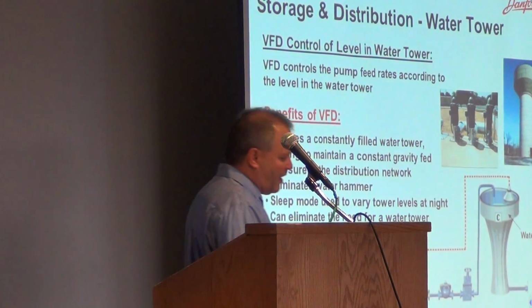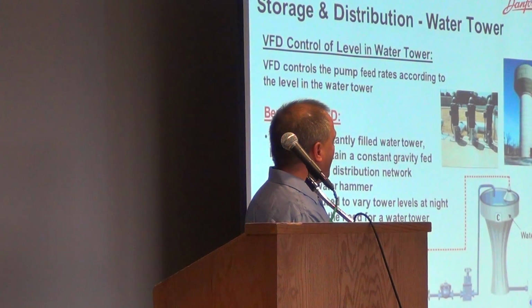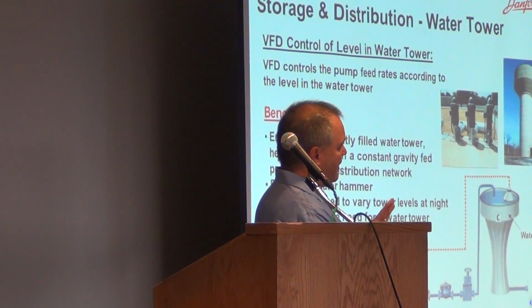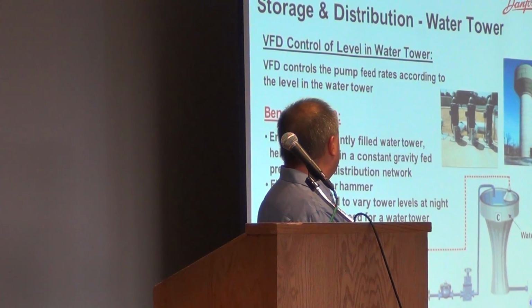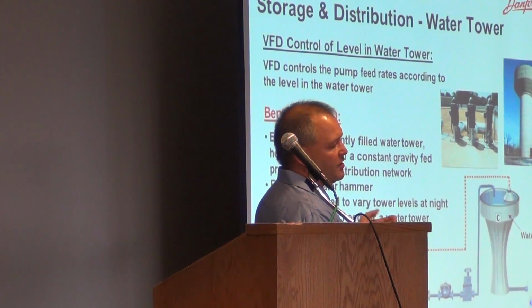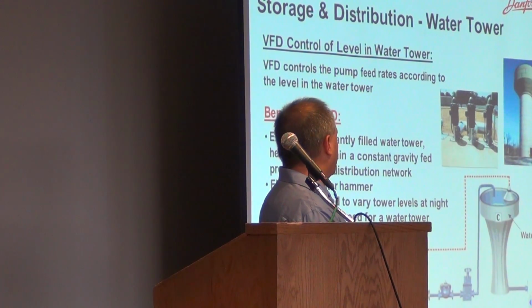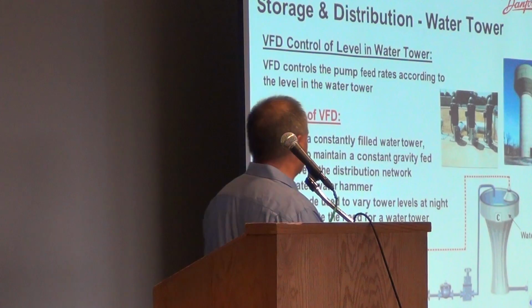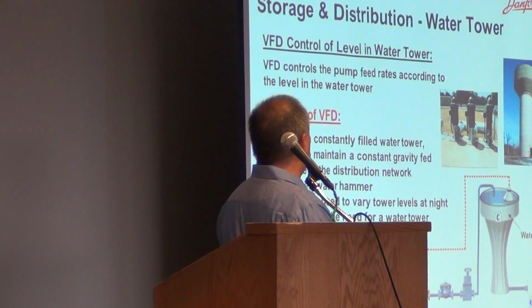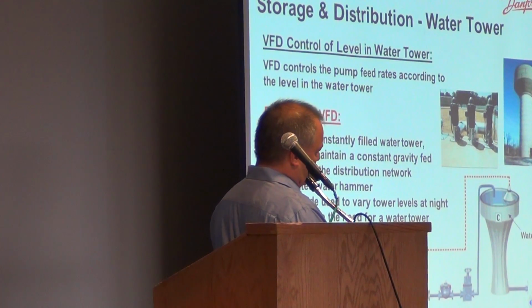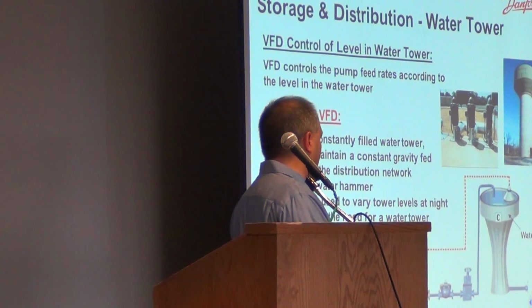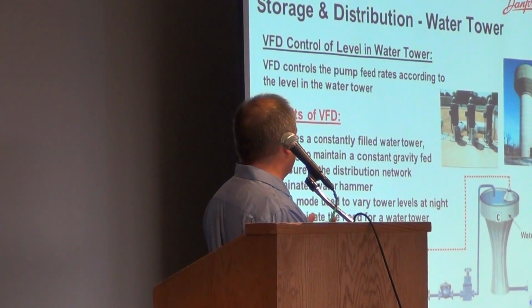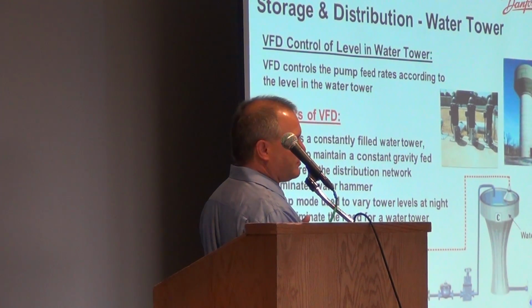Storage and distribution, as we said, we can control the flow. Our drives, I know some of you stopped by, have 4 different setups inside of them. So if you're working with a water tower system, you could have 4 seasons. You could have your spring, summer, winter, and fall levels with a flip of the switch or the digital input from your SCADA system. Eliminating water hammer to the water tower, a lot of them are open discharge from the water tower, so that really doesn't happen too often, but when the water tower gets to full level, a lot of cities, we go at night a lot of times. It's just easier. You can actually program the drive to only run at certain times of day.